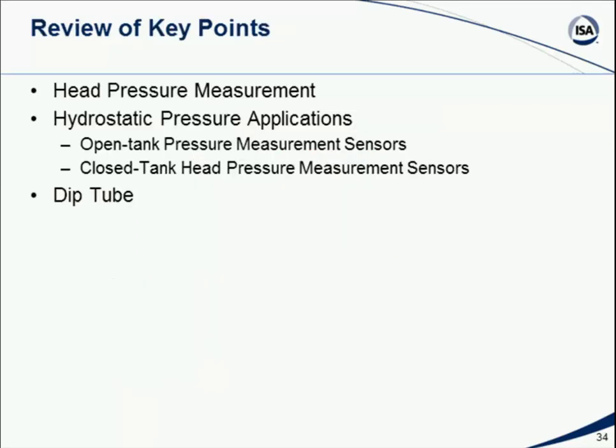All right, so hydrostatic pressure measurement. It works off of the basic principle that a column of fluid exerts a downward pressure or force, and that pressure or force is going to be proportional to the height of the column and the specific gravity, or the weight per unit volume, of the fluid. So a heavier fluid is going to push down and have a greater pressure than a lighter fluid. So a foot column of water will give me a certain pressure. The same foot column of mercury will give me a much greater pressure, and the same foot column of jet fuel will give me a lesser pressure because it's got less density.